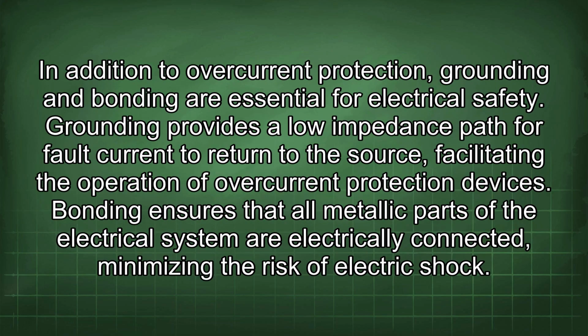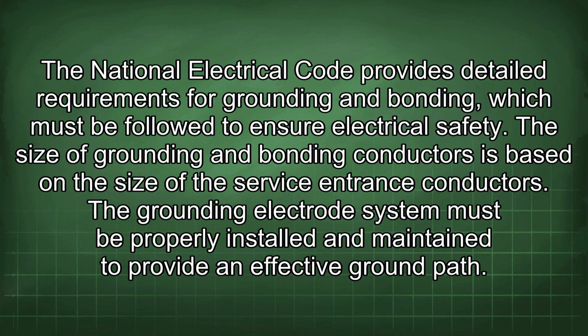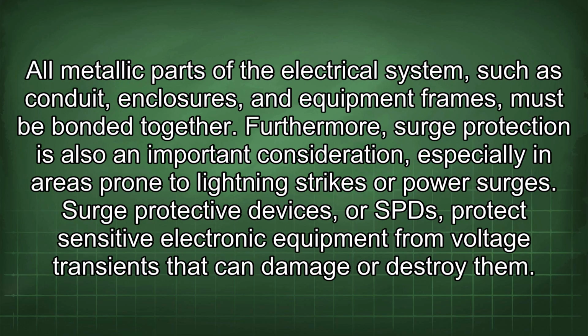In addition to overcurrent protection, grounding and bonding are essential for electrical safety. Grounding provides a low impedance path for fault current to return to the source, facilitating the operation of overcurrent protection devices. Bonding ensures that all metallic parts of the electrical system are electrically connected, minimizing the risk of electric shock. The National Electrical Code provides detailed requirements for grounding and bonding, which must be followed to ensure electrical safety. The size of grounding and bonding conductors is based on the size of the service entrance conductors. The grounding electrode system must be properly installed and maintained to provide an effective ground path. All metallic parts of the electrical system, such as conduit, enclosures, and equipment frames, must be bonded together.